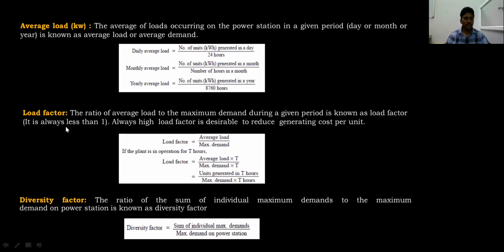Next one is load factor. The ratio of average load to maximum demand during a given period is known as load factor. Load factor is equal to average load divided by maximum demand. Maximum demand is always greater than average load. Therefore, load factor is always less than 1. But the desirable thing is to get a load factor near 1. It is desirable for a power plant, to get maximum output.